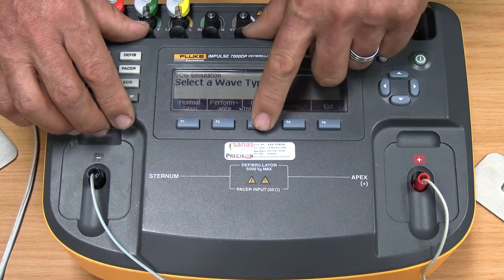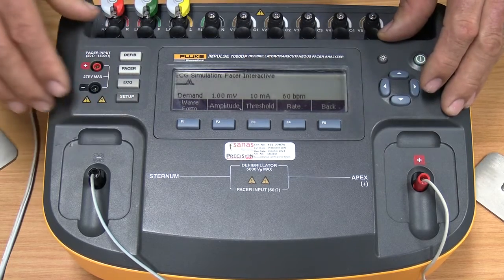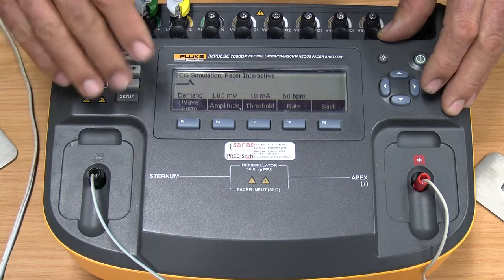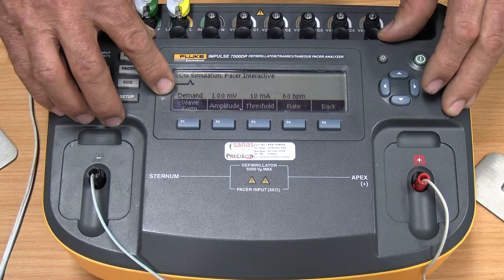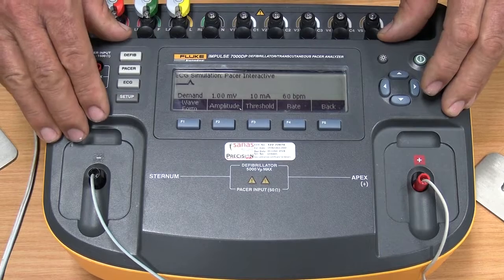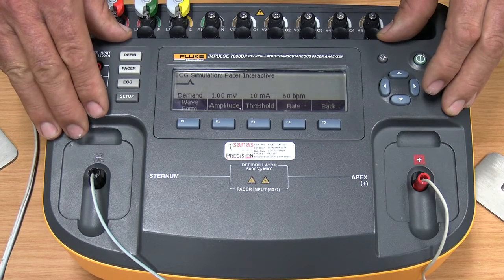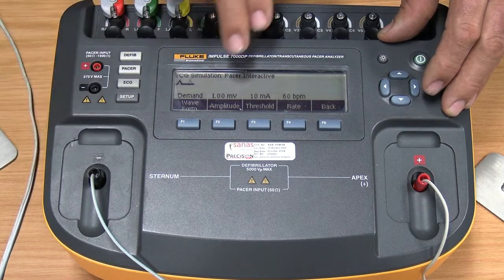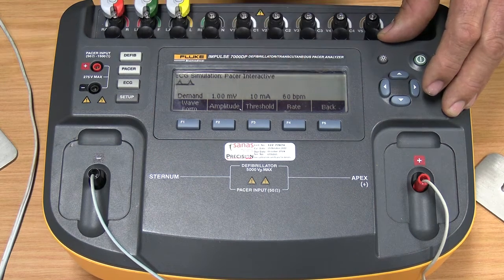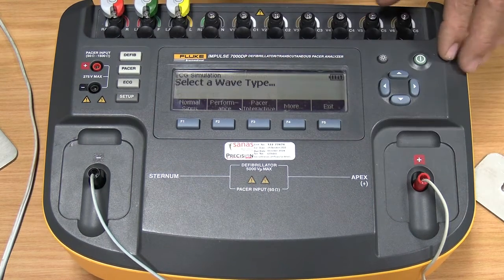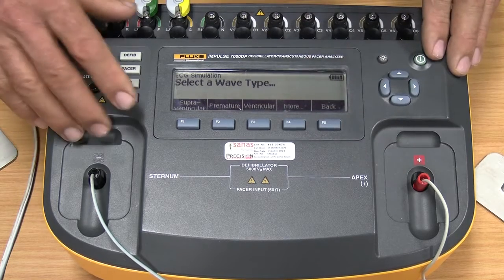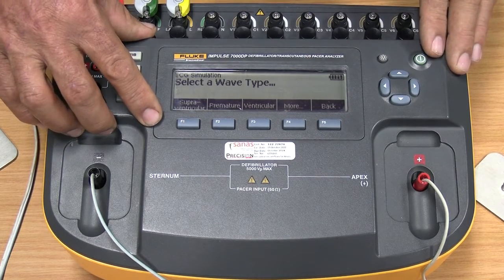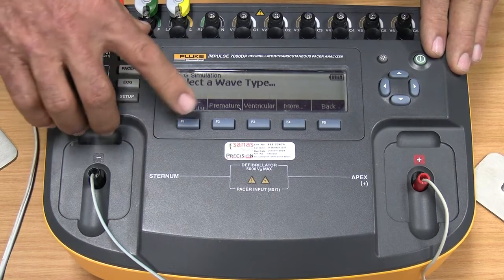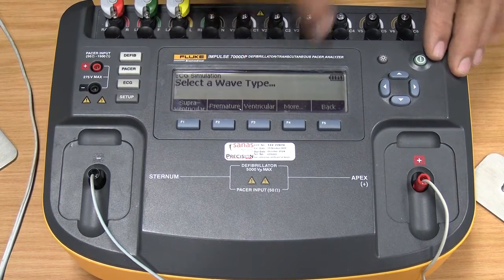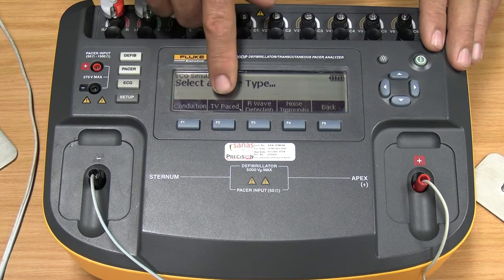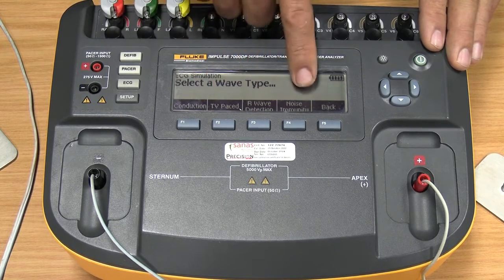Then pacer interactive. That is when you want to set a demand mode for your pacer, meaning you want to set a rate that's lower than your defib pacer is set to, to see whether the pacer comes in. And the same there, you've got an amplitude, a threshold, and a rate that you set. Go back. If we go to the More button, this is now where you start to get more arrhythmia type waveforms, like your supraventricular, your prematures, your ventriculars. If you go to more, your conductions, your TV pace, your R waves, and so on.